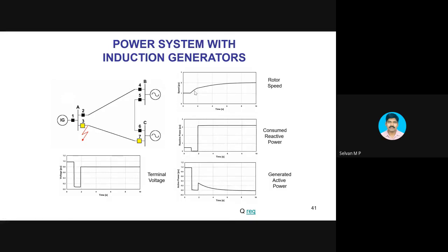So what happens even after clearing the fault? Even after clearing the fault, the voltage comes back to 0.8 per unit. But during that time, the machine speed has gone up enormously. This machine, the squirrel cage machine, is called a fixed speed generator. It cannot operate beyond a certain slip. It will keep on running, but it won't provide any real power.